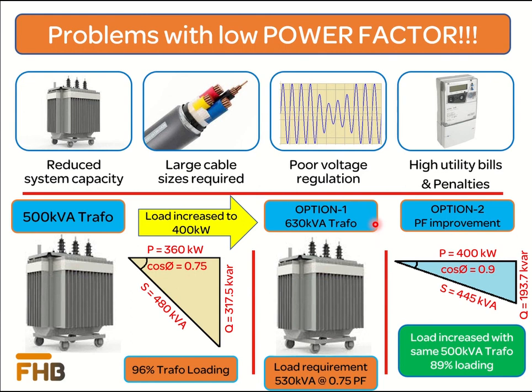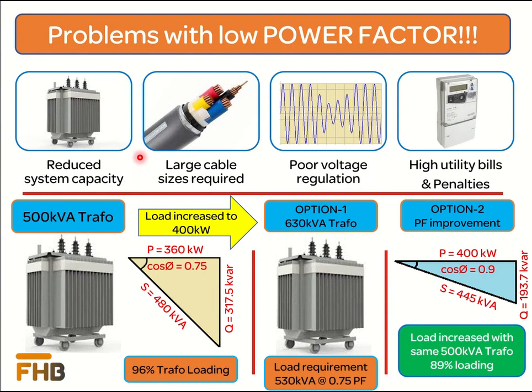To cater to this increase in load, we have two choices. The first option is to replace the existing 500 kVA transformer with the next available size of 630 kVA. The second option is to improve the power factor — using the commonly targeted value of 0.9. At 0.9 power factor and 400 kilowatt connected load, the kVA requirement reduces to 445 kVA, which is only 89% loading of the existing 500 kVA transformer. Lower power factors require larger and more expensive installed equipment.